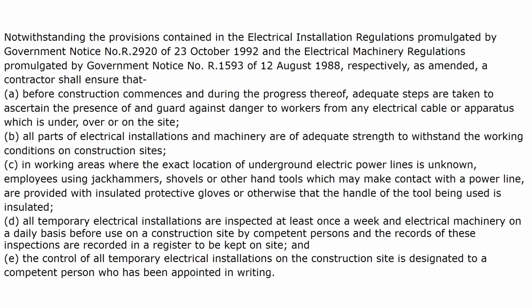(b) All parts of electrical installations and machinery are of adequate strength to withstand the working conditions on construction sites. (c) In working areas where the exact location of underground electric power lines is unknown, employees using jackhammers, shovels, or other hand tools which may make contact with the power line are provided with insulated protective gloves or otherwise that the handle of the tool being used is insulated. (d) All temporary electrical installations are inspected at least once a week and electrical machinery on a daily basis before use on a construction site by competent persons, and the records of these inspections are recorded in a register to be kept on site. And (e) the control of all temporary electrical installations on the construction site is designated to a competent person who has been appointed in writing.